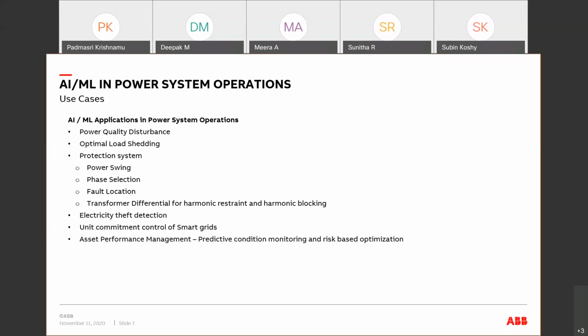But apart from that, the amplitude and the sequence component of the current have many shortcomings when it comes to distributed energy resources. When you are looking at a negative sequence current, and you make a phase selector based on the presence of the negative sequence current above a certain value, then with distributed energy resources, especially solar or wind, the inverter comes into the picture. When the inverter comes into the picture, there is in general a suppression of the fault current, and the negative sequence current will not reach the threshold at all. So you always have a problem with the phase selection then.